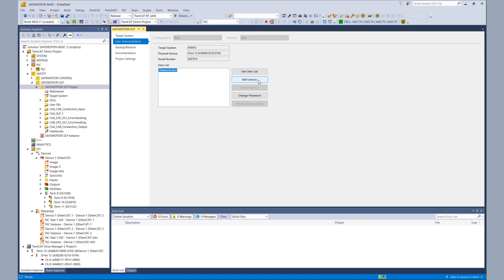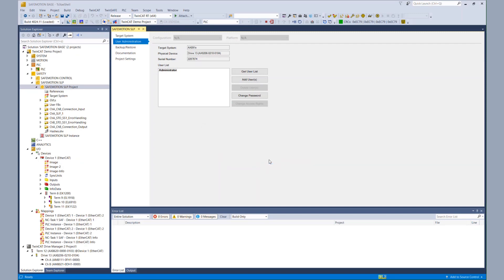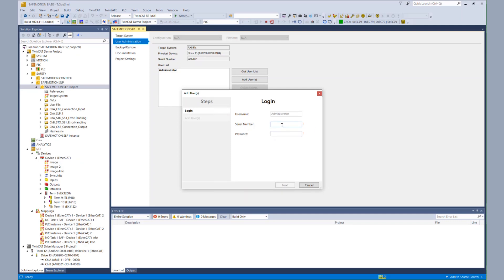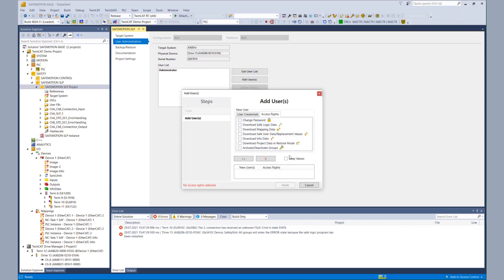We get the current list of users and create a new user. This warning only tells you that if you do user management, the safe communication will break down. Now we have to log in for the user management via serial number and password. We put in our username 'test user' for the new user we want to restore, and we create the password. In the next step, we configure the user rights. Our user has every right except the download of the project data in restore mode. So now we put in the user rights and we can finish the user administration.